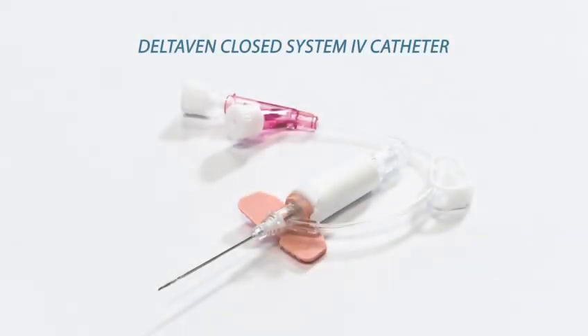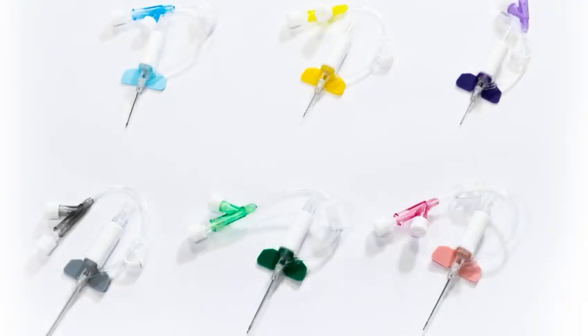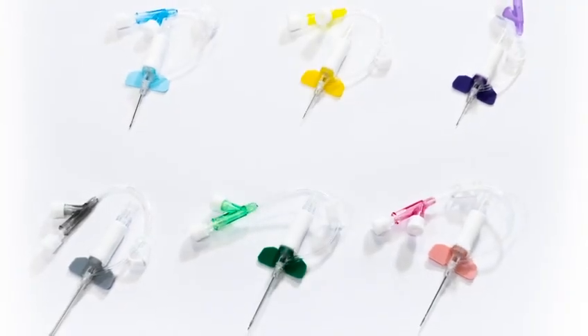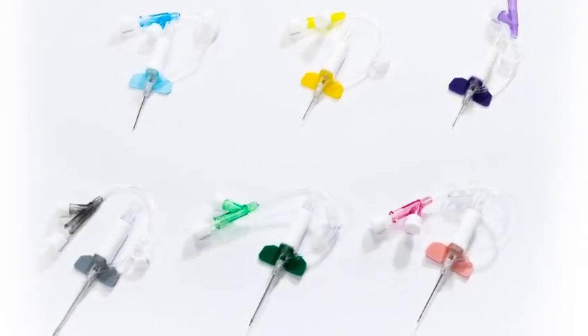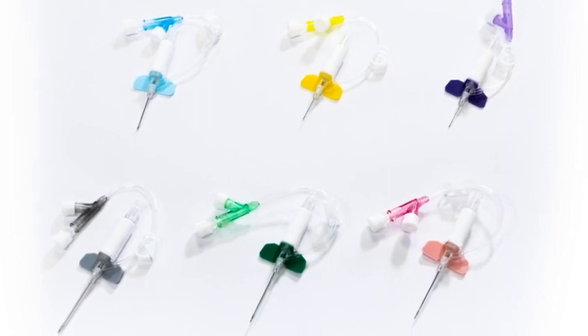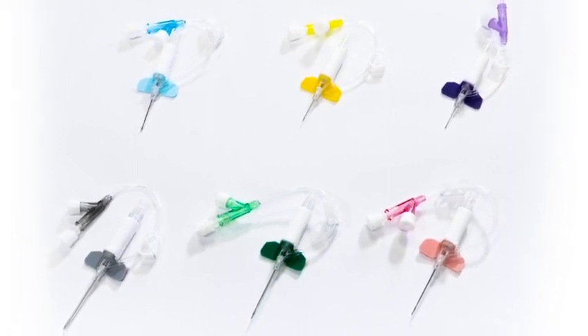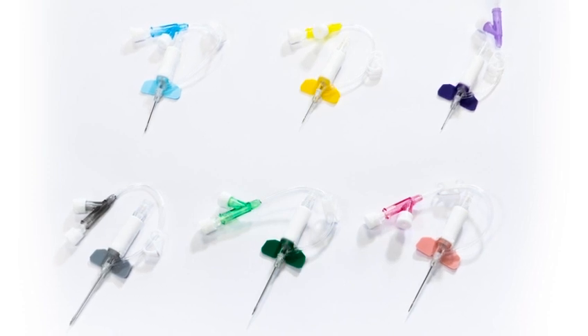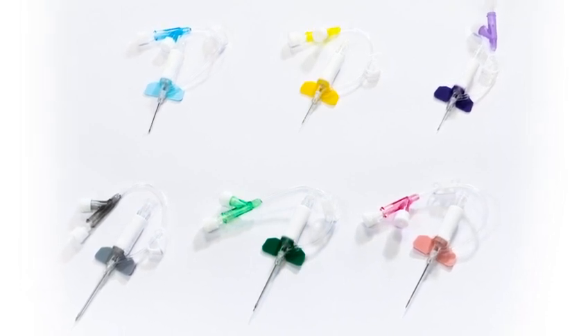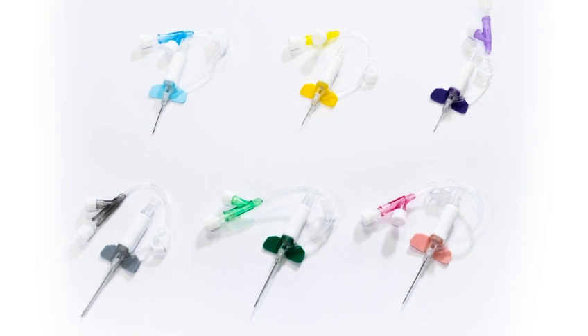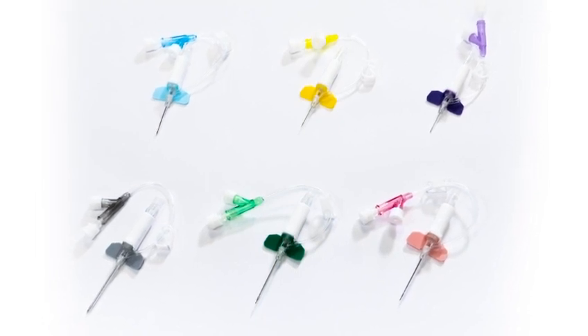Deltaven with fast flash technology is a closed-system IV catheter with integrated passive safety device designed to minimize blood exposure and reduce accidental needle stick injury. The Deltaven with fast flash technology is available in a full range of sizes from 26 to 16 gauge in a variety of lengths. Gauge sizes 24 and larger are rated for pressure injection up to 325 psi.